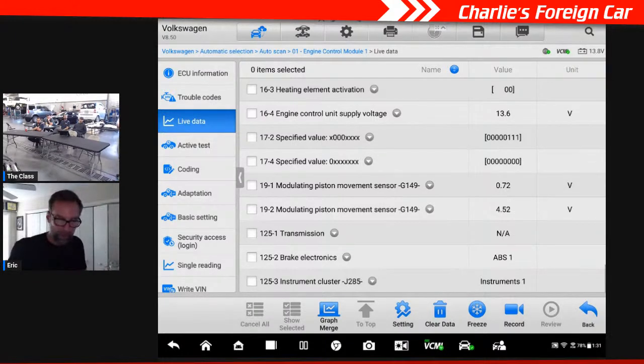Yeah. But it doesn't, I mean, 10 millibar is not ideal, but I wouldn't say that's a fault per se. But what's going on with that voltage? Do we have enough, do we have a 5-volt reference that's fluctuating or low? We have a ground issue on that sensor. Is there other harness issues down the way? That's kind of where we want to look at that. And then...